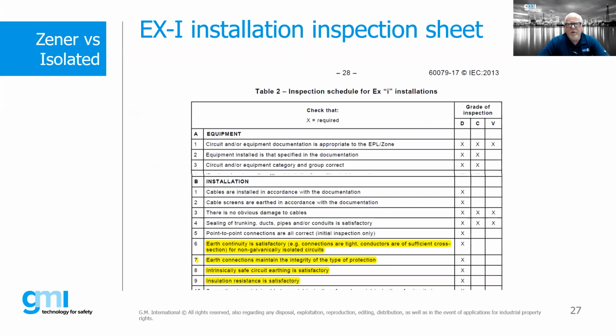This is the inspection schedule that you will find in IEC 60079-17. And actually, we have now adopted this in the United States as a UL standard. This is telling us the specific requirements, that we do have to make an earth continuity check for non-galvanically isolated circuits. So, is the insulation resistance satisfactory? Is the earthing satisfactory? This is part of our detailed inspection when we bring IS loops into service, and it is a requirement under the -17 standard. So it's not just me telling you this, it is actually written in the standards and is part of the requirements when we use IS circuits, and specifically these are the ones that would apply to a non-galvanically isolated system.